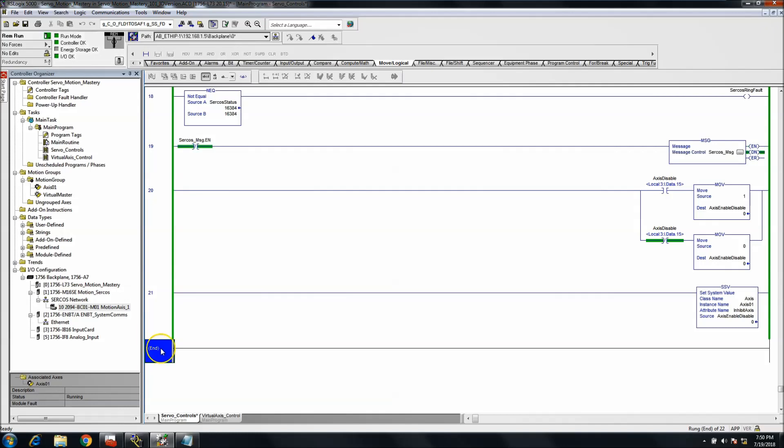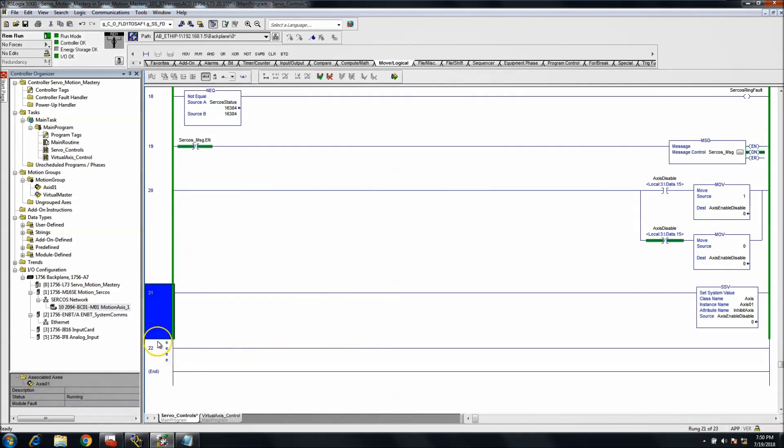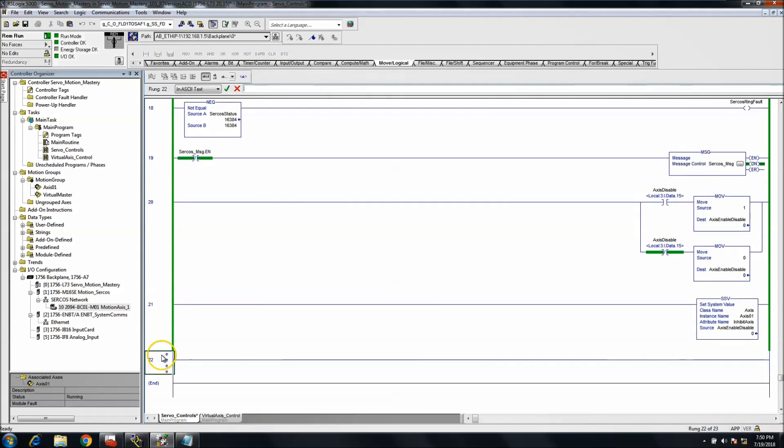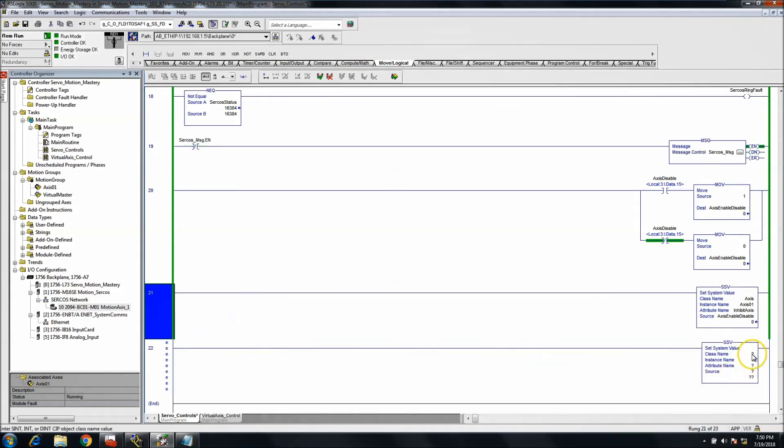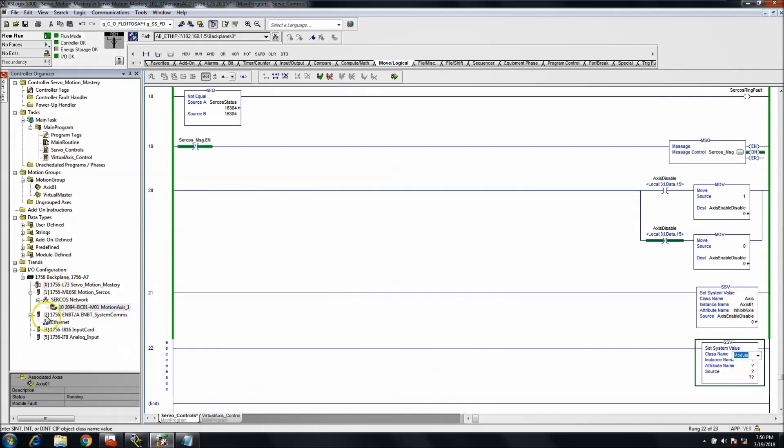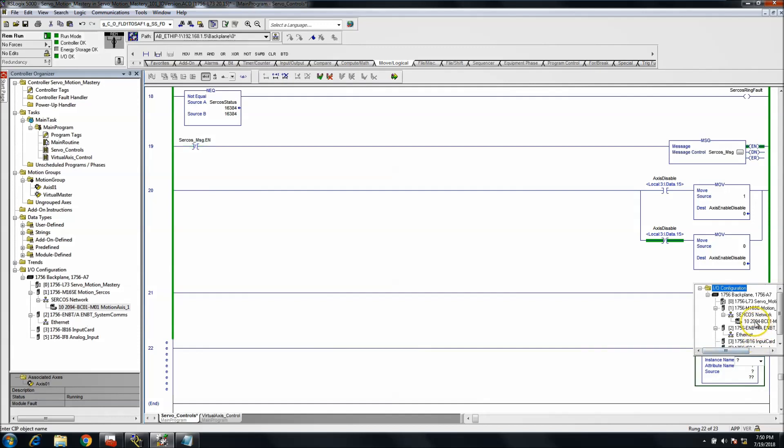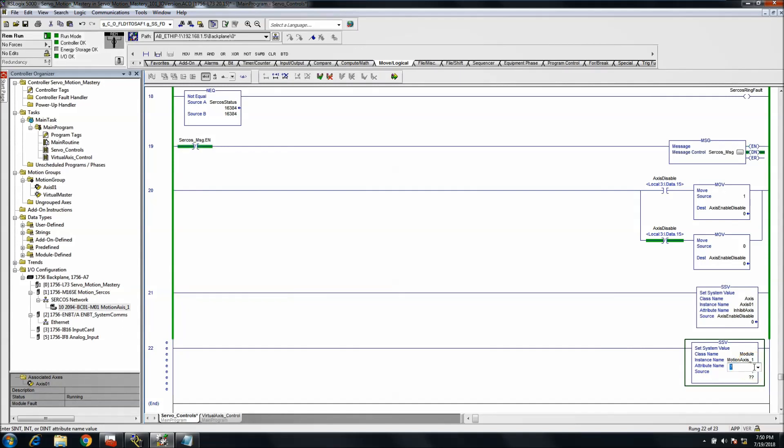So what we'll do is we'll go ahead and add that SSV in here. And then the class that we're going to use, this is going to be a module. So instead of being an axis, it's going to be a module because we're going to point to our IO module, which would be our Kinetix 6000. The instance we're going to use is where we're going to point to the module that we want to use, which we're going to point directly to our controller, our Kinetix 6000. The attribute name that we want to do is the mode. So we want to actually control the mode of what it's doing.